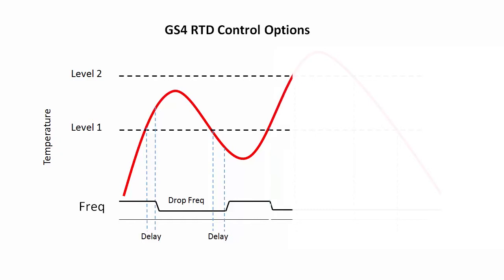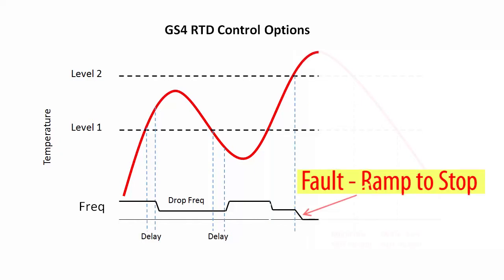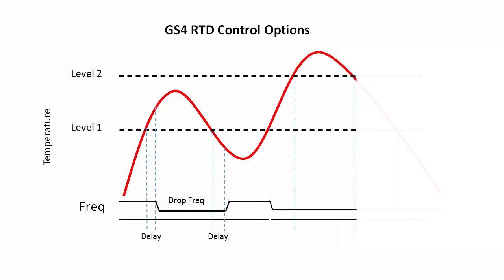If the temperature reaches level 2, the drive does whatever parameter 639 says it should do. It could just issue a warning, issue a fault and ramp to a stop, issue a fault and coast to a stop, or do nothing. Once the temperature reaches level 2, the only way to get the motor to resume normal operation is to clear the fault – it doesn't automatically recover like the level 1 condition did.